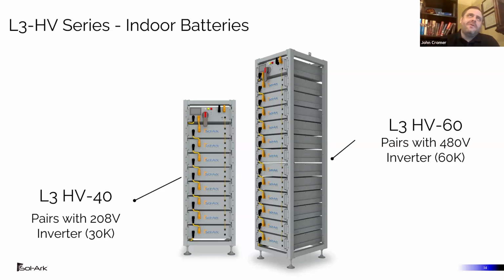And when I say indoor, yes, I do mean inside the building in a control room or a secured area, but this might also be outside the building if you're building your own battery cabinet or bringing your own container, building your own battery room. Because it's simple. There's no dip switches. It's automatically configured, so you're really just building the rack, plugging the modules in, snapping in the connectors, running the home runs to the inverter, plugging in the communication system, and then pressing the power button and turning it on. It's specifically built for the battery inverter pairing.